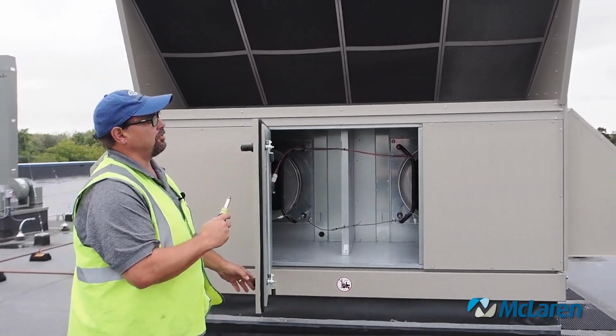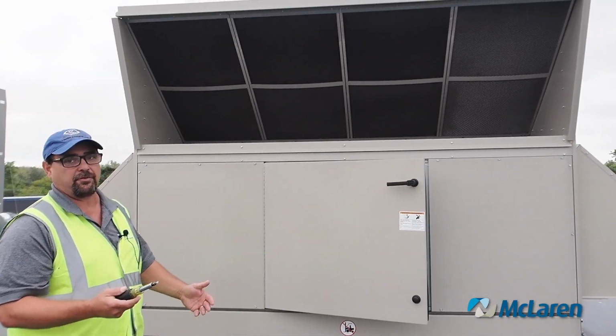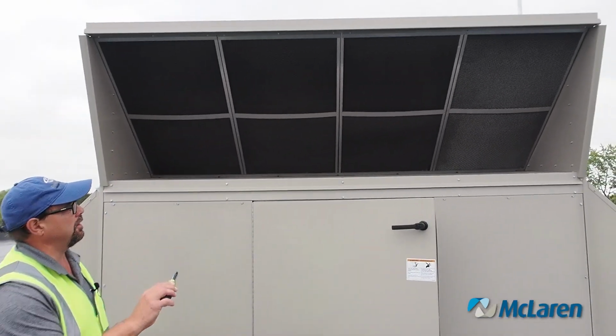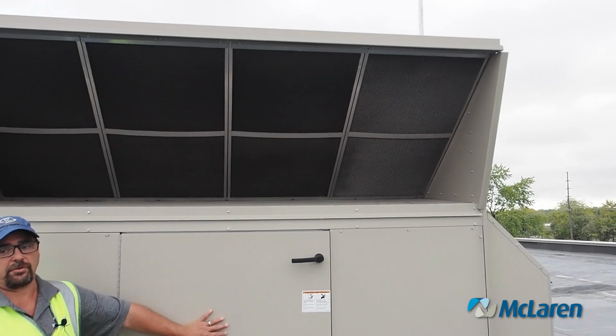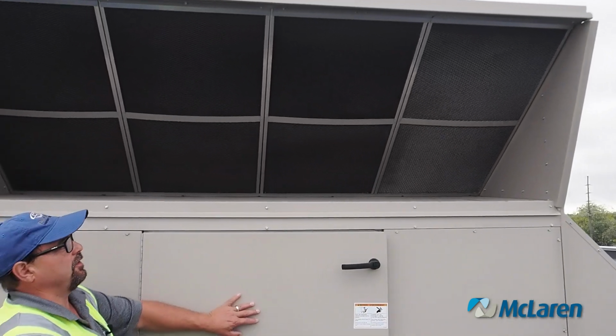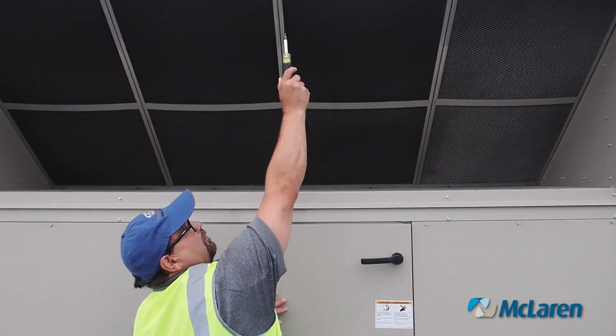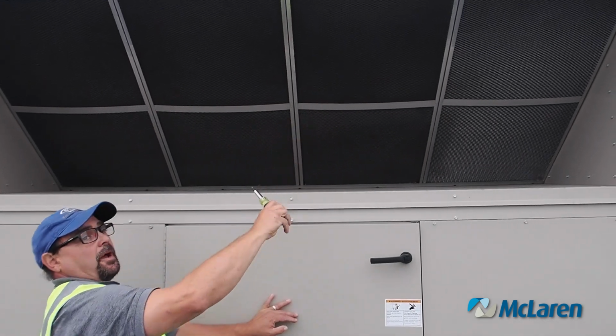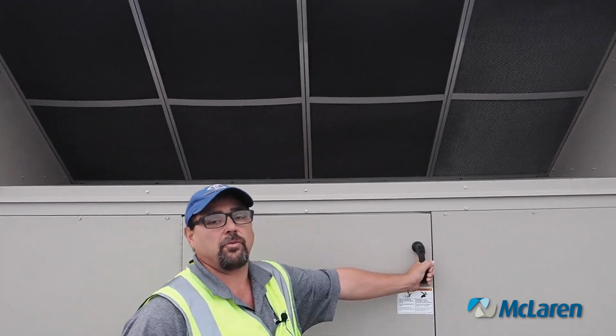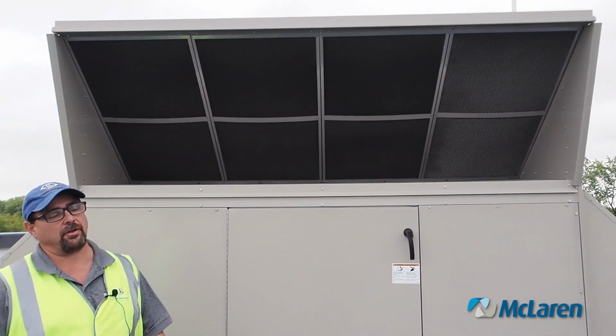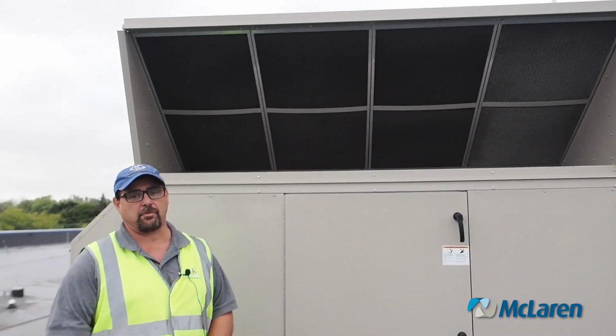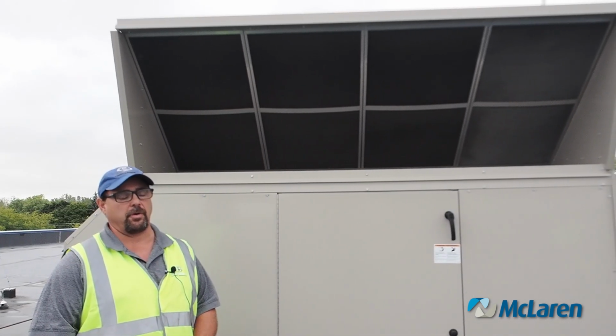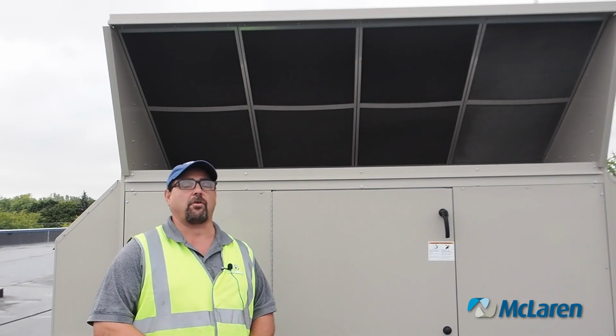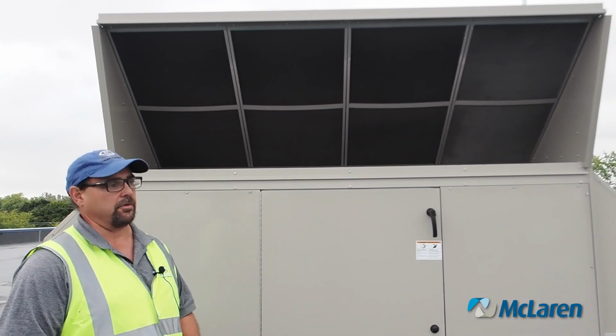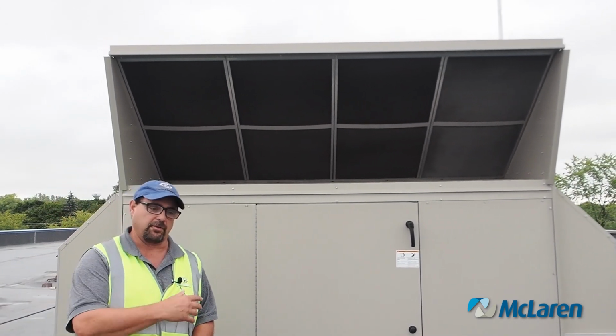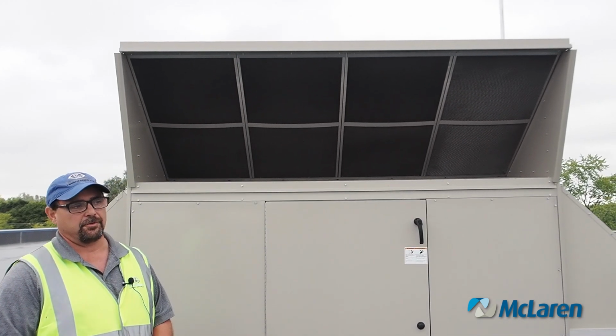Up above is what I call bird screens or leaf screens. The air enters the unit from here, but periodically, and again this is a visual, this isn't a timed thing, these screens are going to have to be washed. All you do is unscrew the top brackets, they drop down and the filters come out. Just a good rinsing. Unless they get neglected, you don't have to use a pressure washer or chemicals on them. If you do it on a regular basis, then just a gentle hose. And I tap all the water out and dry them the best you can, because it could get sucked into the filters and cause a mess too after you wash them.